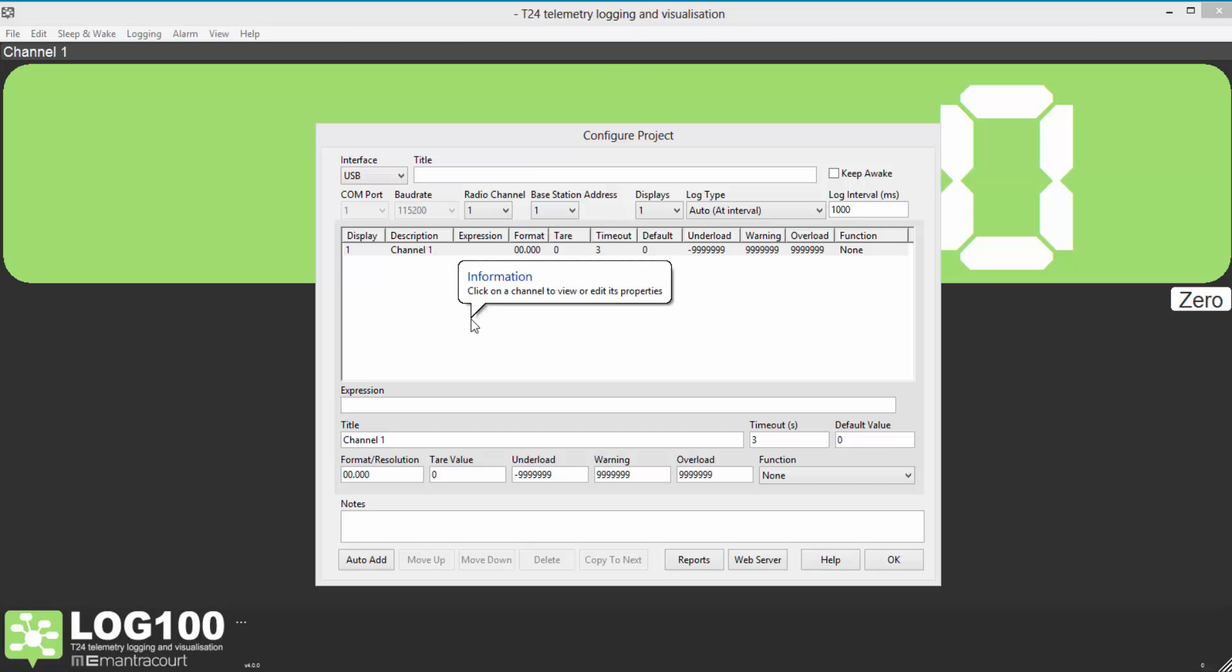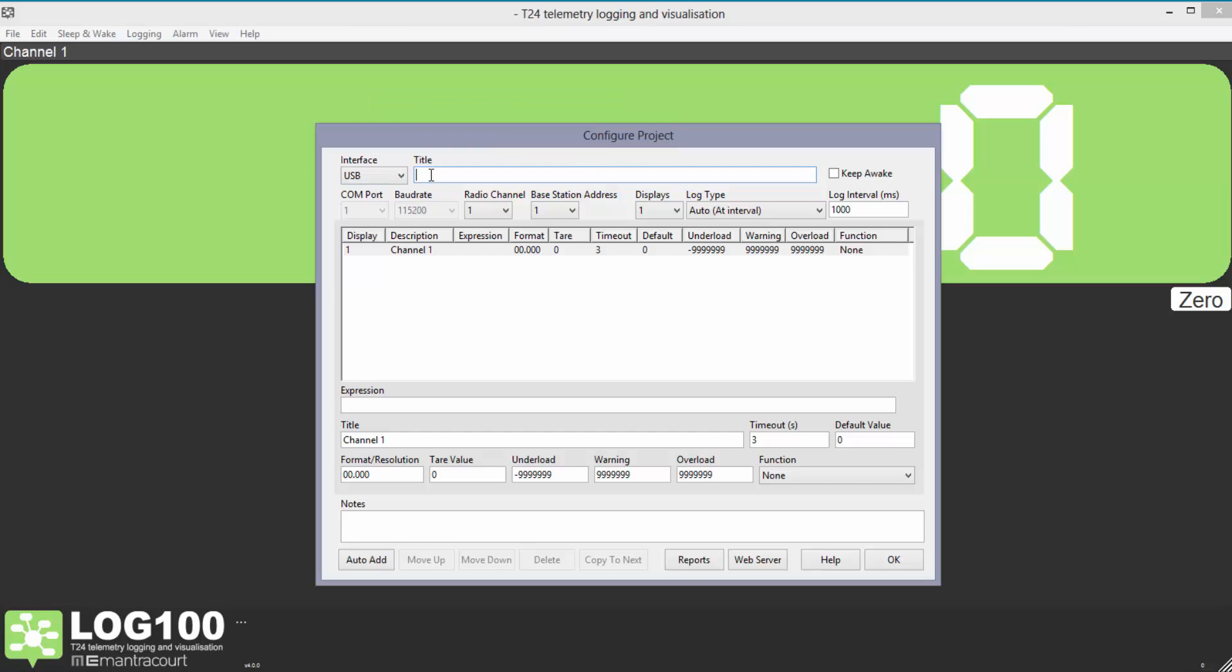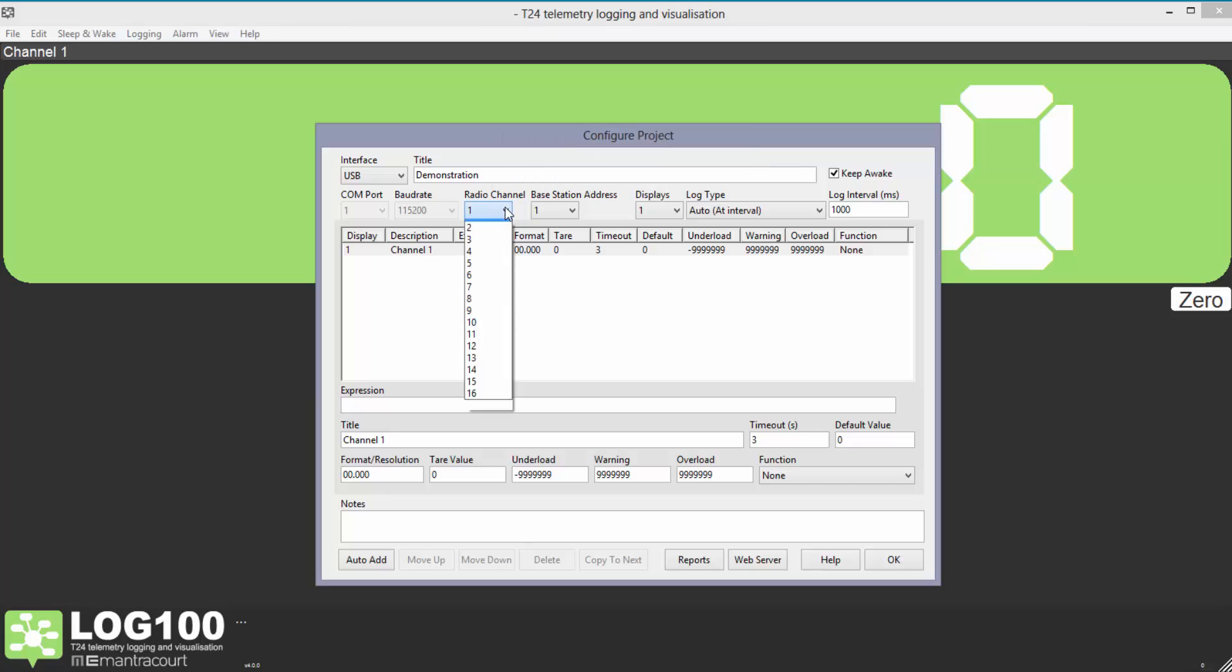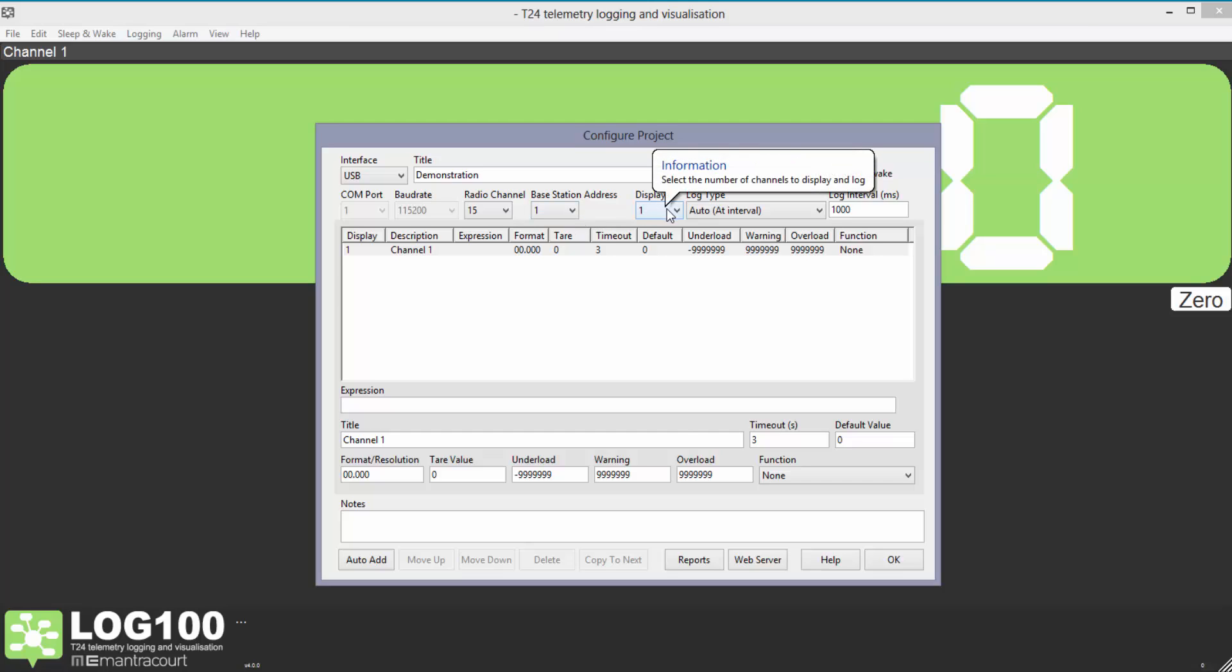Along the top we select the base station type and give the project a name. If you want the modules to stay awake whilst Log 100 is running tick the Keep Awake box. As we're using a USB base station we cannot change the COM port or baud rate. The radio channel must be set to the same as the modules that are being monitored. When using multiple base stations it will be necessary to enter the address here. Otherwise the default should be 1.